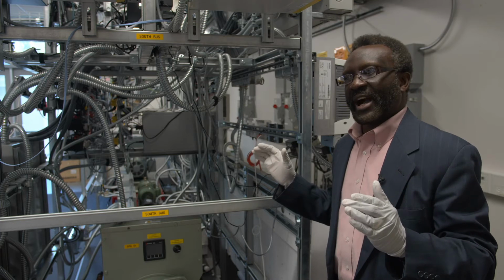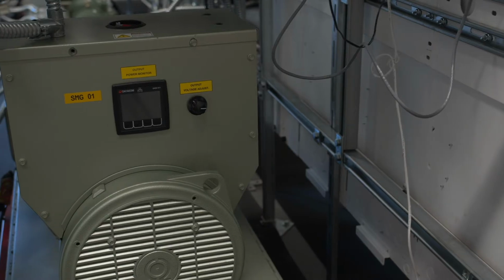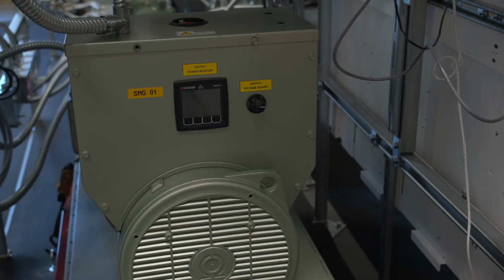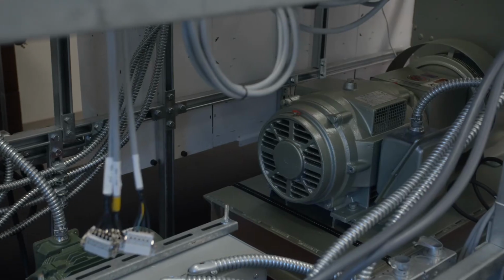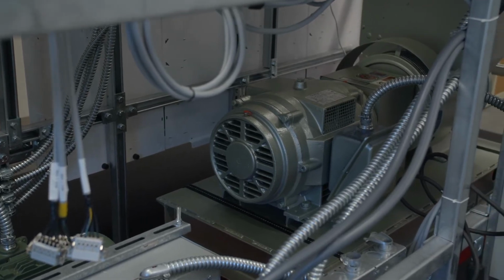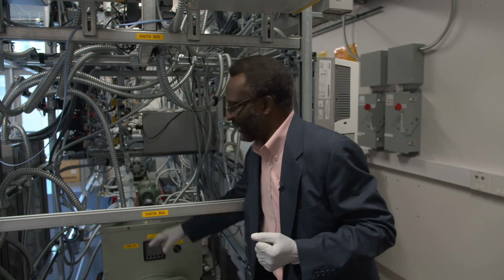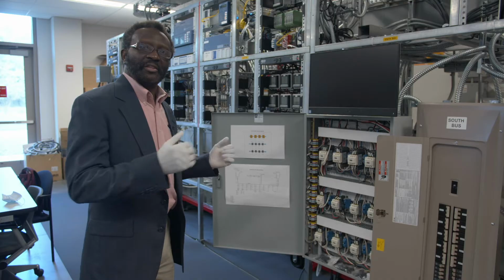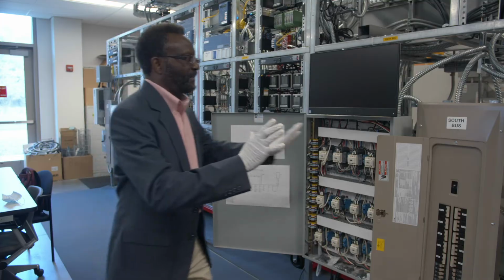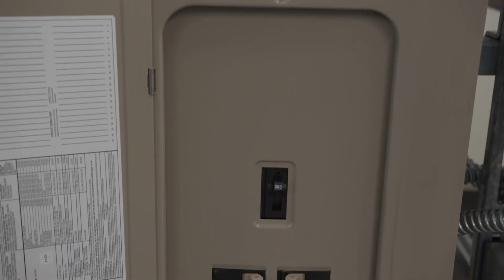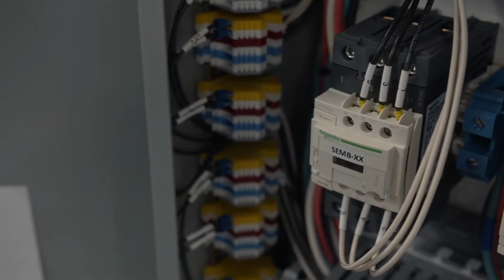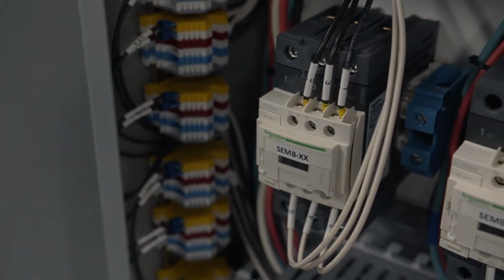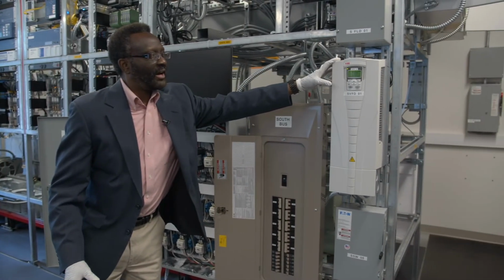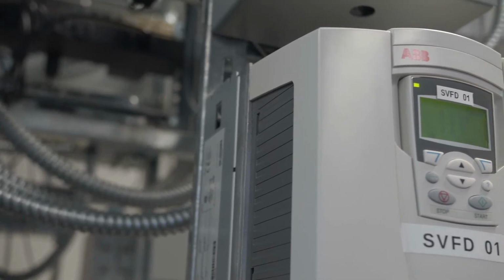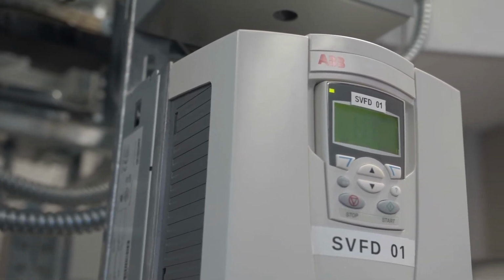Each bus has a conventional generation system. For us, the generator simulating the electrical utility's generator is a motor generator set, which is a combination of an induction motor driving a synchronous machine. We have one of these on each bus. The generator on this bus is connected to the physical 3-phase bus, and these are the electromagnetic switches controlling the different breakers on the bus. This is an adjustable drive that we use to control or regulate the generator.